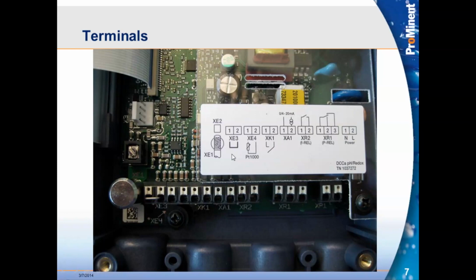So those are our inputs, and you see that the inputs are kind of below the terminal strip. Then we'll talk about the outputs, and they tend to be indicated above the terminal strip, so it's less likely to confuse that. So here, XA1, we have the milliamp output. Typically, we're going to use 4 to 20, but you can see you can scale it to be 0 to 20. And again, that can be either a measured value output or a control output.